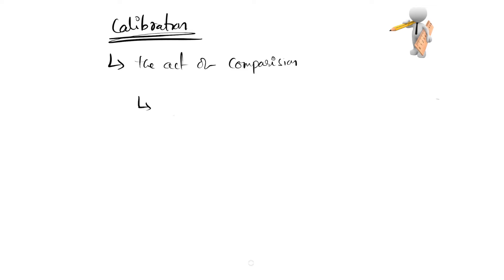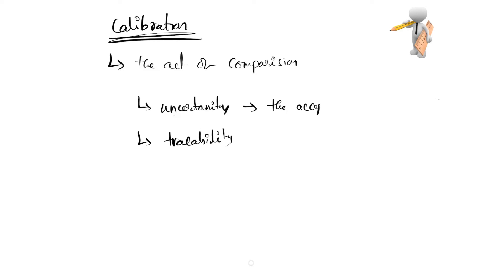There are two principles involved in ensuring whether the instrument is giving correct results or not. Those are uncertainty and traceability. Uncertainty is the acceptable error associated with the measuring instrument.